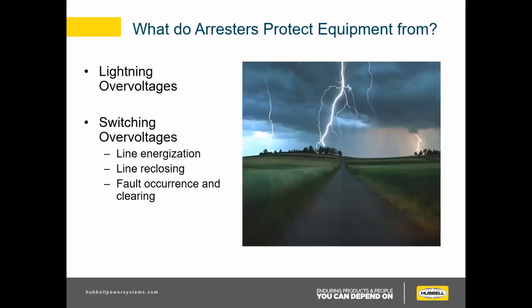So what do arrestors protect equipment from? The first thing that probably comes to mind is lightning. A lightning arrestor is a common name. They also protect against switching overvoltages. And this is generally for more of a station geared topic, but line energizations, reclosings, fault occurrence and clearings, as well as switching series capacitors are all things that an arrestor will take care of and keep out of the system.